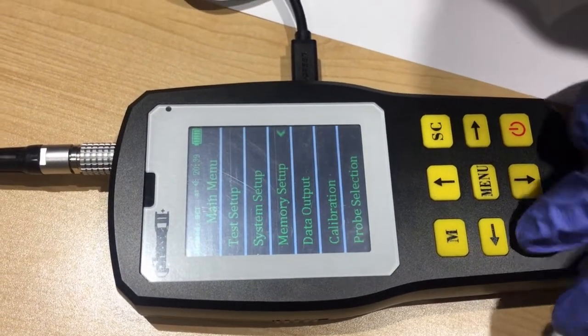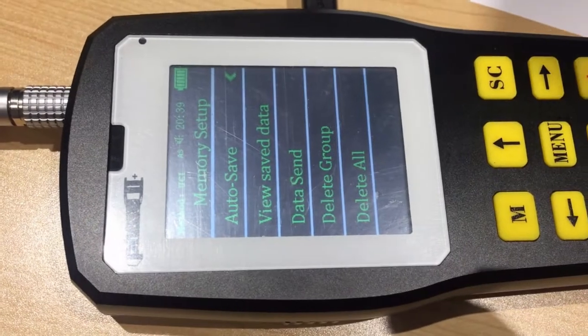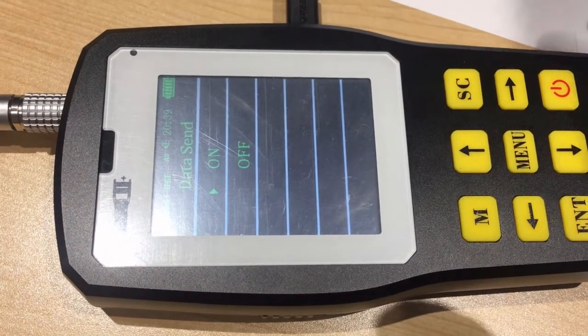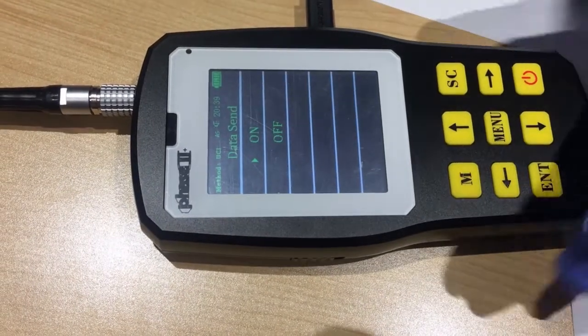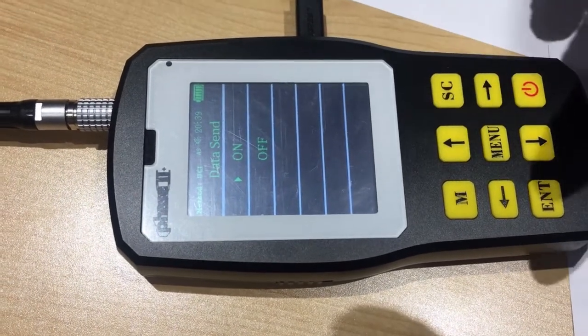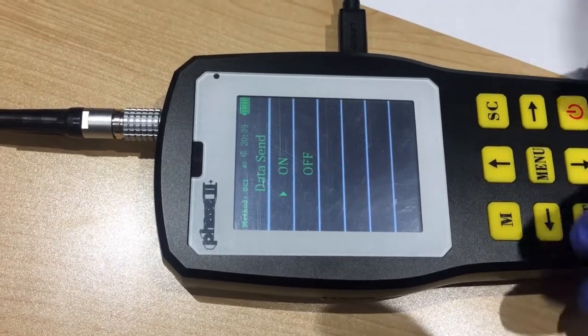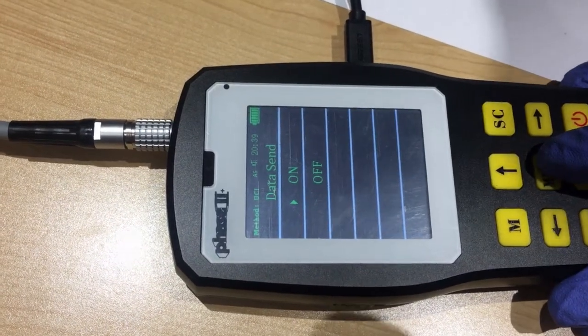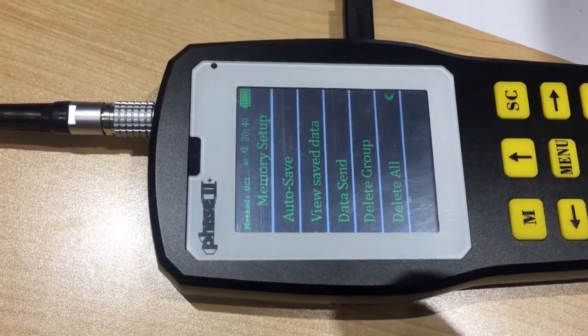The memory setup here is something very important, because you want to read your data to the PC to save it. And you must use this function. Data Send, you can choose it on or off. If you choose it off, the data will be saved in the machine, and it allows at most 2,000 groups of data. After that, the data will be automatically deleted. And if you choose on, your data will be transferred to your computer if you are linked. Here you can delete the groups you don't want, and also you can choose to delete them all.